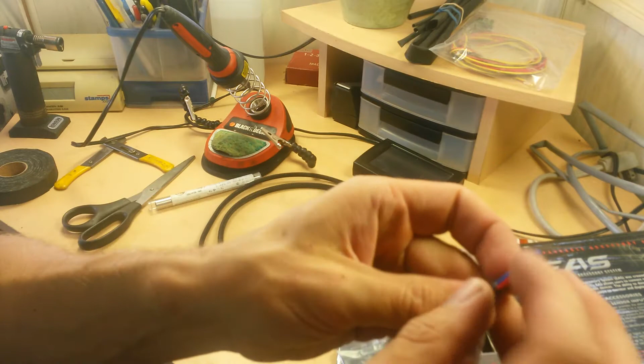They're 3-wire sensors, 5-volt pressure transducers. That means you have a VREF signal, a ground, and a sensor output signal. These particular sensors run from 0.5 volts up to 4.5 volts, so 4.5 volts will be the top of the pressure scale. On a 100 psi pressure transducer, 4.5 volts would be 100 psi, and 0.5 volts would be 0 psi. Check out my other videos for the setup of the EAS system, how you properly set it up to work with a standard transducer.